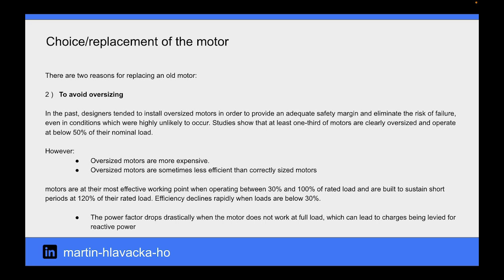Motors are at their most effective working point when operating between 30% and 100% of the rated load and are built to sustain short periods at 120% of their rated load. Efficiency declines rapidly when loads are below 30%. The power factor drops drastically when the motor does not work at full load, which can lead to charges being levied for reactive power.